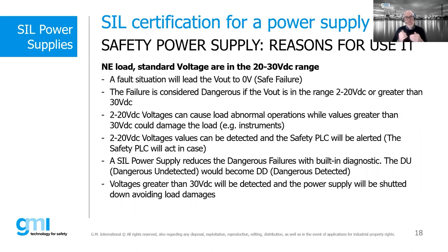At this point, why is it important to use a safety power supply system in our application? First of all, we know that the standard voltage for a normally energized load is in the 20-30 volt DC range, a condition that leads to power supply output voltages between 2 and 20 volt and higher than 30 volt DC being considered dangerous failures, which negatively affect the application. Well, a safety power supply significantly reduces and detects dangerous faults thanks to a built-in diagnostic system. In fact, if an anomalous output condition is detected by the safety power supply diagnostic, it brings the output to 0 volts, which represents the safe fault condition.